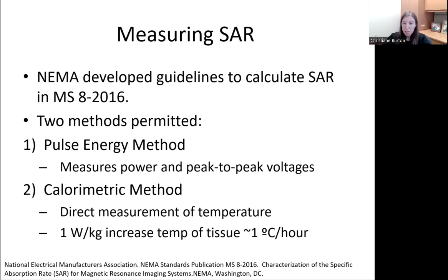The next one is the calorimetric method, which is more straightforward, and as the name suggests, it uses an insulated loading phantom with direct measurement of temperature. From the degree of temperature increase, the absorbed energy and SAR can be computed. As a crude approximation, a SAR of 1 watt per kilogram would increase the temperature of an insulated slab of tissue by about 1 degree Celsius per hour.